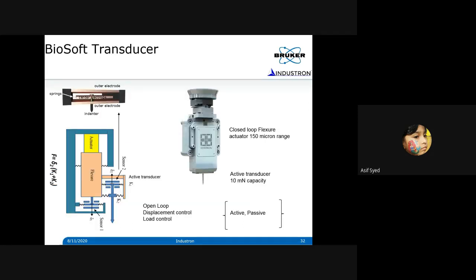Okay, so I mentioned that we need to have a unique transducer. That's what I am showing you in a schematic way. The BioSoft transducer works on a different principle. Up till now, whatever I presented, we used an electrostatic force actuator transducer, where you generate the force electrostatically and measure the displacement capacitively. That transducer is good, but when you try to understand the properties of soft materials, I mentioned that you need to have very large throw, which means very large displacement in hundreds of microns. That is not possible with that transducer, because the plate gaps, the spacing between those plates, are only 60 microns or less. So you can't go beyond that. Only 1/3 of that gap is useful when you make a measurement. So we can't use the electrostatic force transducer for soft materials.